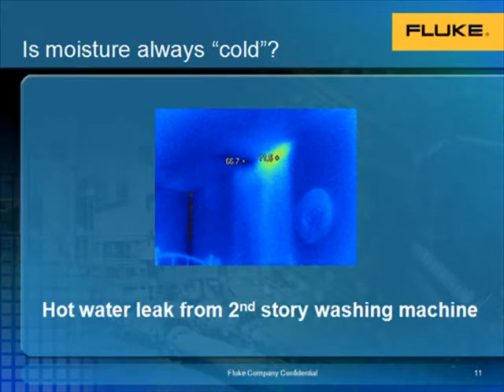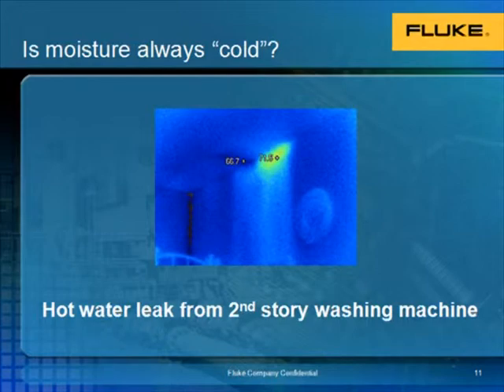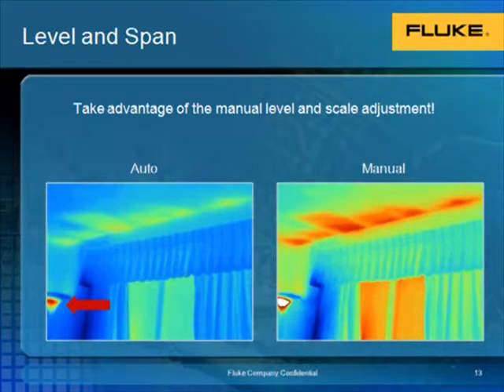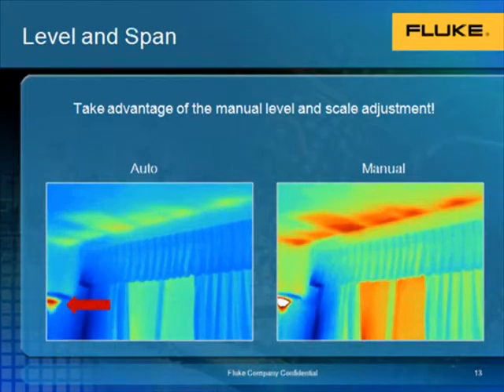Moisture on the interior of a building is not always cold, as you may think. Here we see a water leak from a second-story washing machine, which leads to a thermal signature that is actually warmer than the surrounding wall. The level and span are adjustments that can be made right on board a thermal imager. The span refers to the highest and lowest temperature found within the measurement area or field of view. On the left we see an imager set in auto mode. By setting the span manually, we can saturate out the extreme heat coming from a light and make a much more vivid picture.